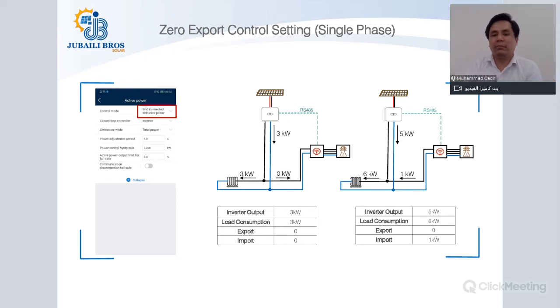All of a sudden, what happens is that this load, which is 6 kilowatt, drops to 3 kilowatt, which is shown in the second SLD on the left side. Since you have configured the zero export control setting in the single phase, what it will do is immediately reduce the power from 5 kilowatt to 3 kilowatt, so that there is no additional power going towards the grid. The arrow shown towards the grid side shows you 0 kilowatt. This is what will happen in a zero export with the total power limitation.